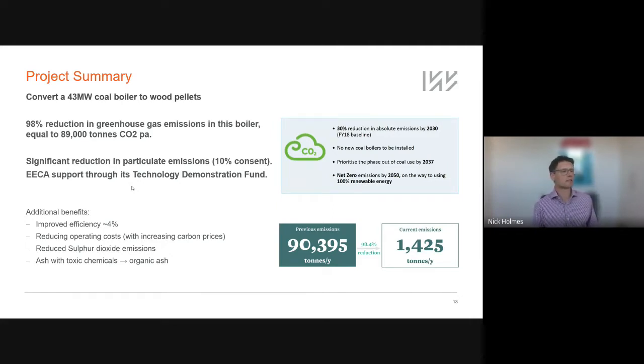There's some other drivers there at the same time. The emission system on this boiler was getting tired. So that was another driver that helped get this over the line, as well as some funding through the EECA technology demonstration fund in New Zealand. Some of the other benefits of what we did: overall improved efficiency, reduced sulfur emissions, obviously removing that coal, and with that the ash that's inevitable with that high ash coal. So that's no longer a problem.